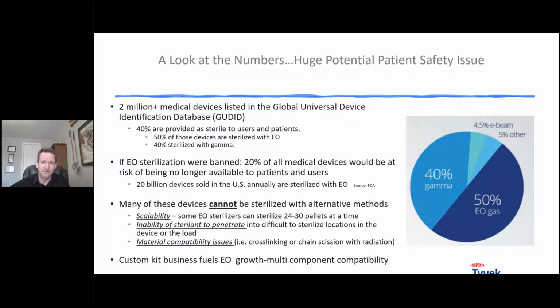Availability: these contract sterilization facilities are all over the US. And the second reason is the inability of these other sterilants to penetrate into some of the hard-to-sterilize parts of the device or the product load itself. When you box it up, put it on a pallet, in some cases maybe it's shrink wrapped, it's just hard for some of these to penetrate as well as ethylene oxide does. Ethylene oxide is a very small molecule, so it penetrates very well. That's probably its biggest advantage, its ability to penetrate through polymers and through a lot of the different plastics.